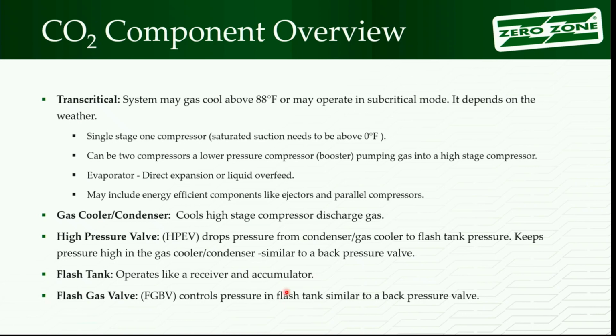If I know it's a transcritical system, I know, okay, it's going to be hot outside. And in the United States, if you do air-cooled, you're transcritical sometime. There's no place in the United States where you're not going to have at least one day, once in a while, that's going to get you that warm. So that's all it really tells you. Transcritical means above 88 degrees, and it means it's not going to be condensing at that point in time.